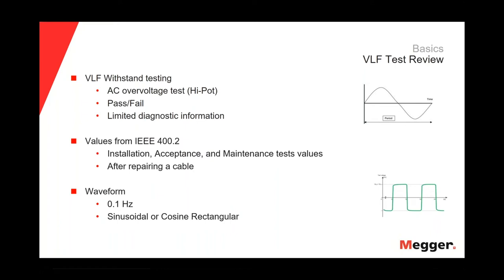The reason I want to do a quick review of the VLF test is because for the tan delta test, we will see later that we will use the sinus wave shape for the tan delta, okay? So, let's start with the cable insulation aging process.